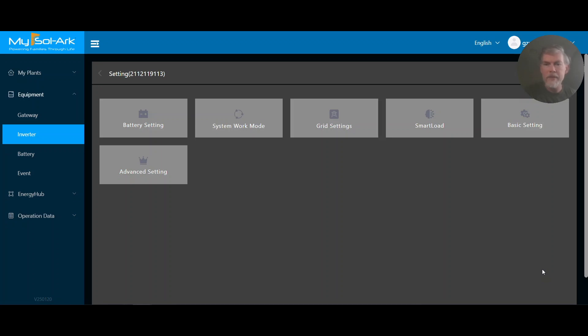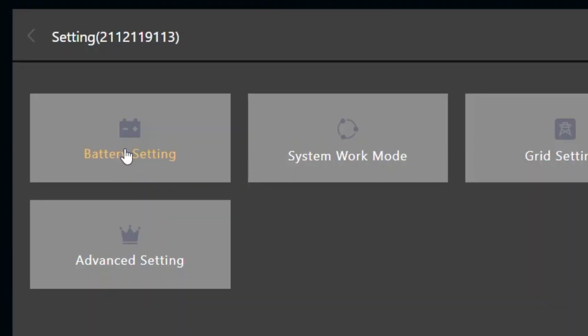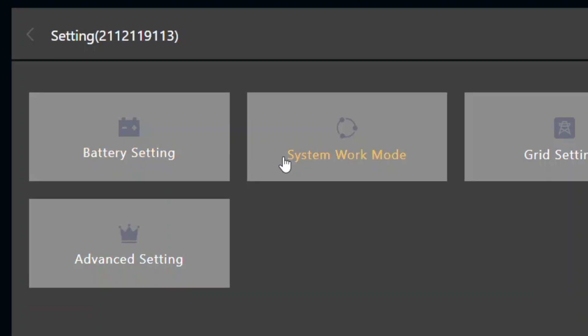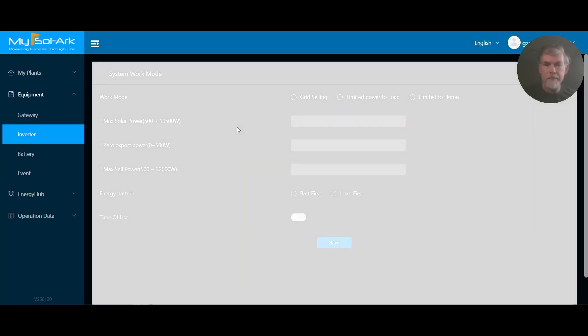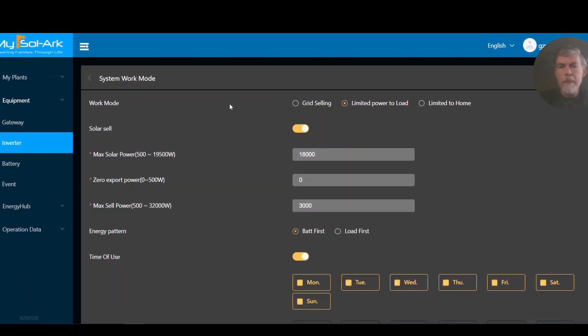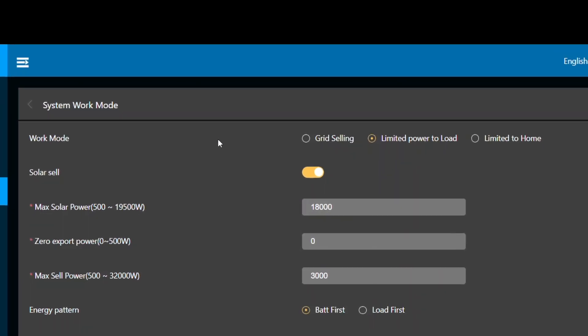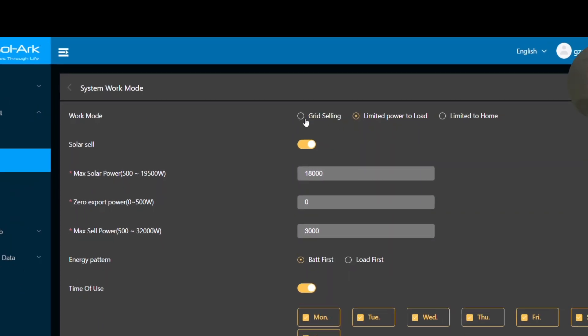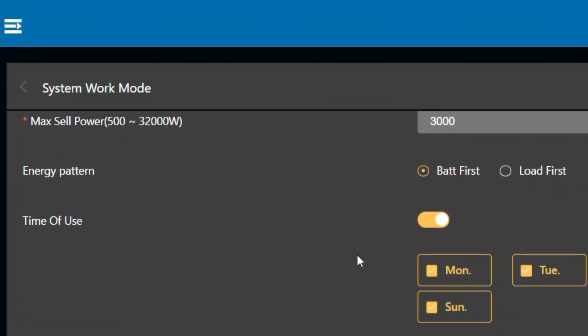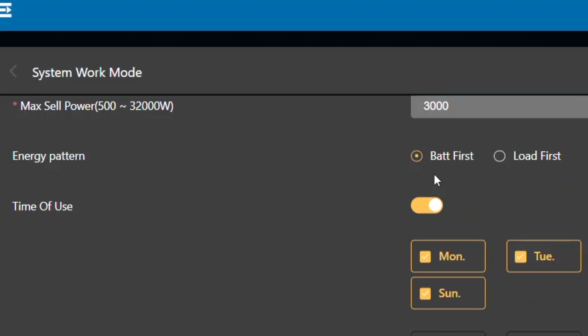Once you're in the parameter settings, these are all the same settings you could adjust on the front of the inverter. The battery settings are already set up — there's a separate video discussing how to do that properly for lithium-ion batteries. The main area we're focusing on is the system work mode. The work mode is very important and needs to be configured based on how your system is set up. For whole-home backup, it makes sense to have 'Limit Power to Load.' There's also 'Solar Sell' if you want to export solar power to the grid, and 'Zero Net Export' as another option. The energy pattern setting lets you choose whether to charge up the batteries or cover the loads first.